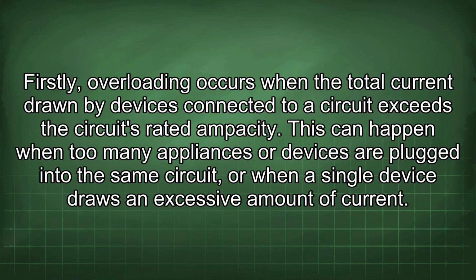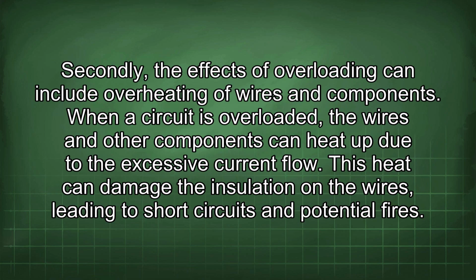Firstly, overloading occurs when the total current drawn by devices connected to a circuit exceeds the circuit's rated ampacity. This can happen when too many appliances or devices are plugged into the same circuit, or when a single device draws an excessive amount of current. Secondly, the effects of overloading can include overheating of wires and components. When a circuit is overloaded, the wires and other components can heat up due to the excessive current flow. This heat can damage the insulation on the wires, leading to short circuits and potential fires.